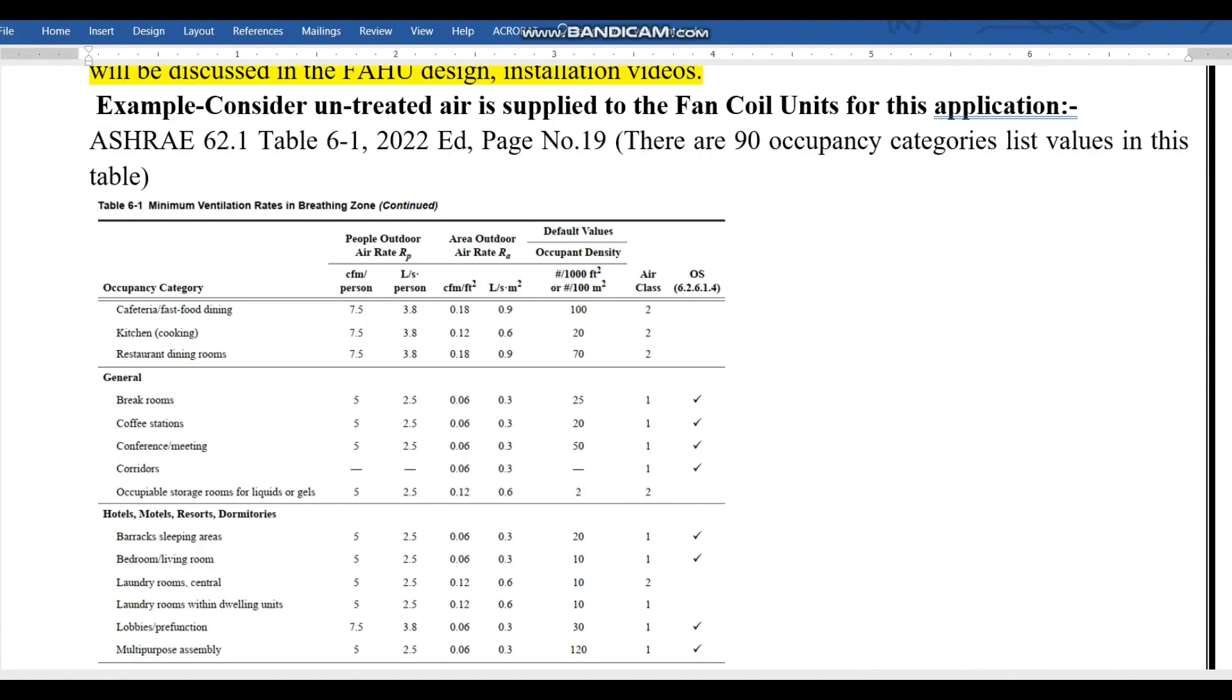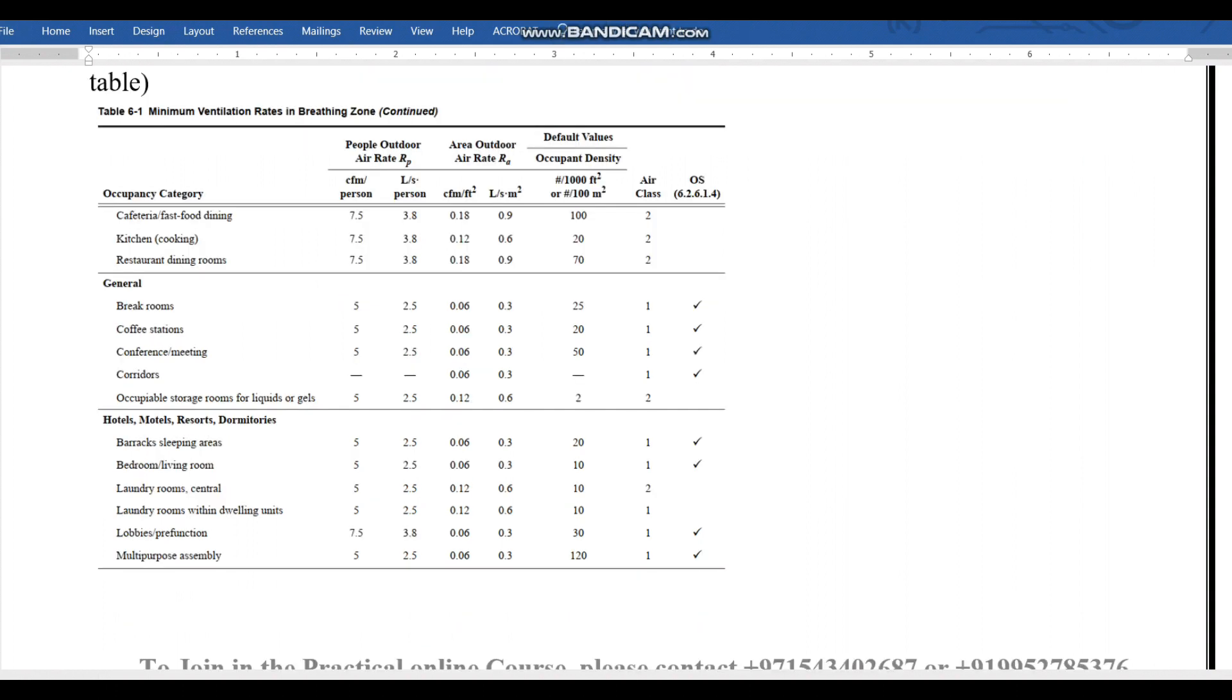If you see ASHRAE 62.1 Table 6-1, 2022 edition, you can see there are total 90 occupancy category lists classified in this table. Table 6-1 is for minimum ventilation rate. If you go to table 6-2, the next table in ASHRAE 62.1, that is for the exhaust air.